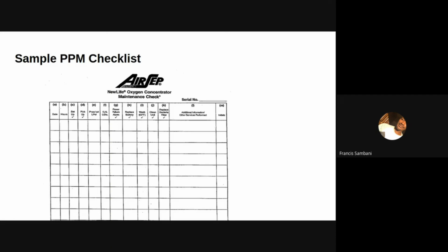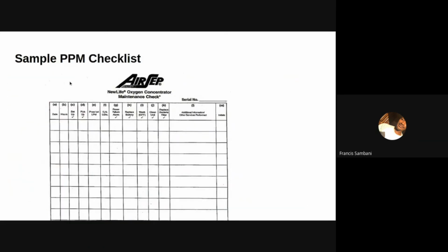And if the power failure alarm was on or not, you're supposed to record that. If you have replaced the battery or not, you're supposed to record that. And also if you have cleaned the unit, you're supposed to check that. And also if you have replaced the bacterial filter, you're supposed to check that as well. And if there's any other additional information, you can write it in the specific cell as well, along with your initials.